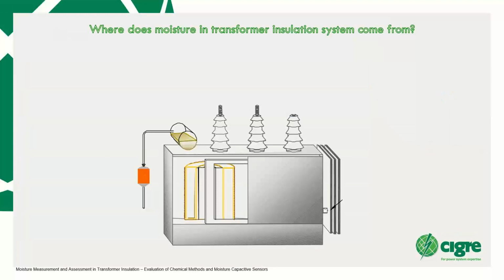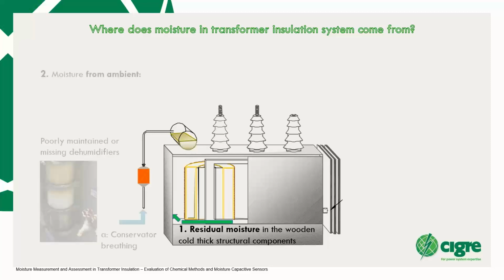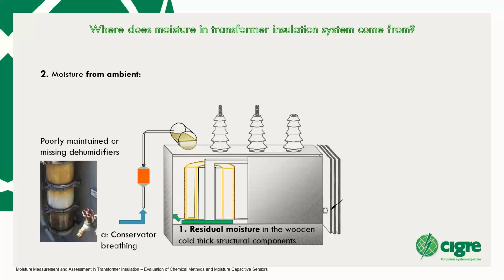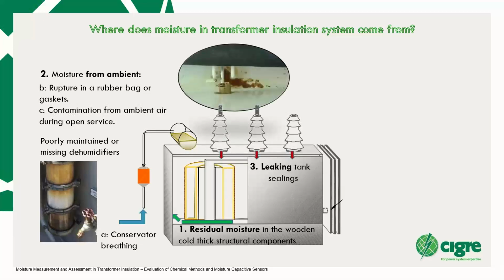So where does moisture come into transformer insulation? There are several ways. First, it can be residual moisture in the wood, cold thick structural components if the transformer has not been dried properly. It can come through poorly maintained or missing dehumidifiers. From ambient air, it can be a rupture in a rubber bag or contamination from ambient air during open service, for example, or leakages—when something is coming out of the transformer, air comes inside and moisture together with it. And aging of solid insulation can also cause moisture increase in transformer insulation.